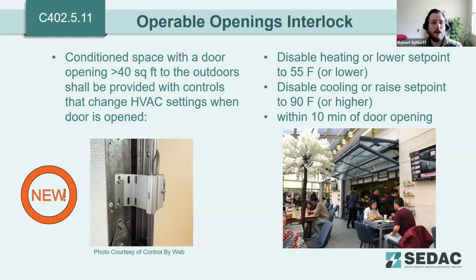So this requirement is operable openings interlock, basically for any conditioned space that has a door opening that is larger than 40 square feet to the outdoors shall be provided with controls that change the HVAC settings when this door is open. These controls must be configured such that they disable the heating or lower the heating set point to 55 degrees or lower. They disable the cooling or raise the cooling set point to 90 degrees or higher, and both of those must be done within 10 minutes of the door opening.